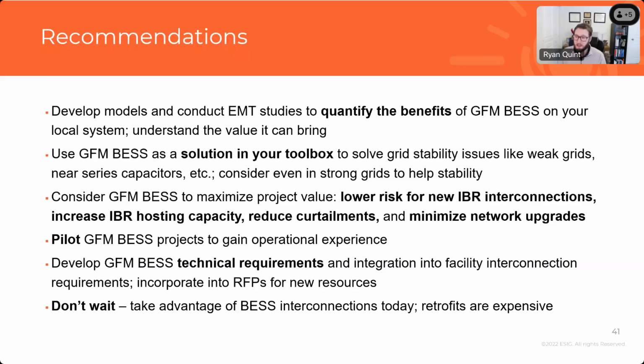It can help maximize project value from a developer's perspective. It could lower the risk of running into stability implications for new IBR interconnections, increase the amount of IBR interconnections within a specific pocket, reduce curtailment under N-1-1 operational conditions, and potentially minimize required network upgrades. So it could be used as a tool for sensitivities. If the network upgrade requires a synchronous condenser, one could ask, well, can we solve that problem with a battery, with a grid forming battery?